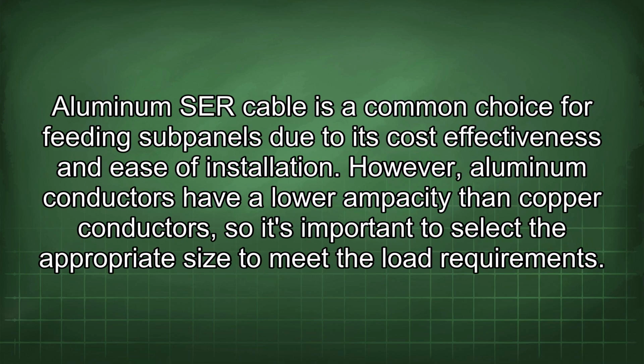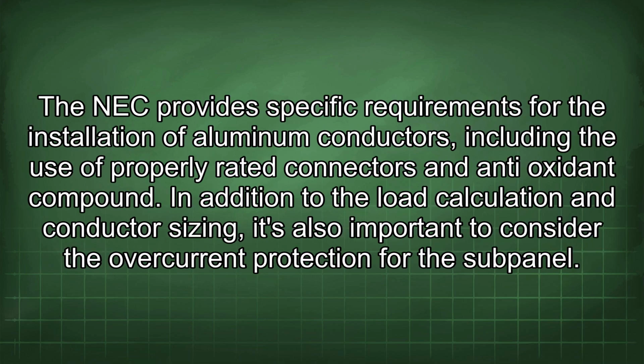Aluminum SER cable is a common choice for feeding subpanels due to its cost-effectiveness and ease of installation. However, aluminum conductors have a lower ampacity than copper conductors, so it's important to select the appropriate size to meet the load requirements. The NEC provides specific requirements for the installation of aluminum conductors, including the use of properly rated connectors and antioxidant compound.